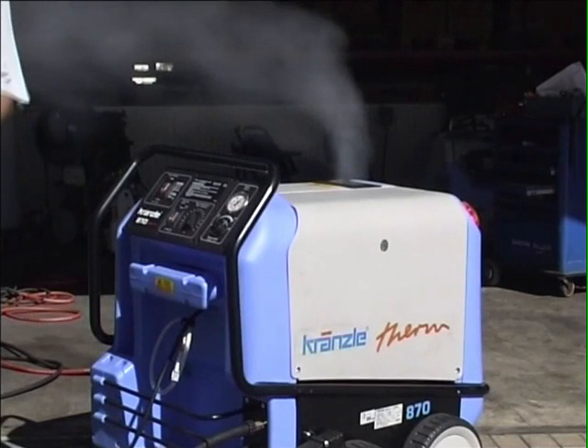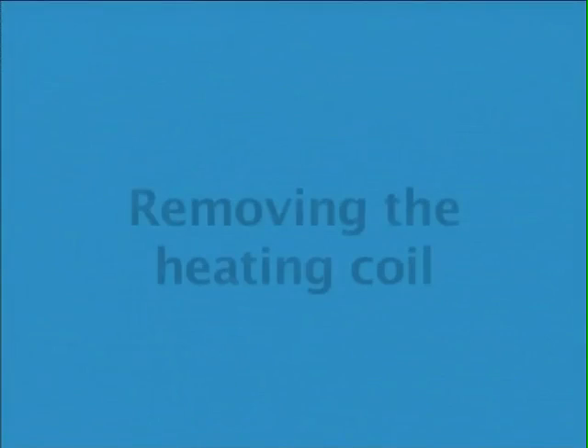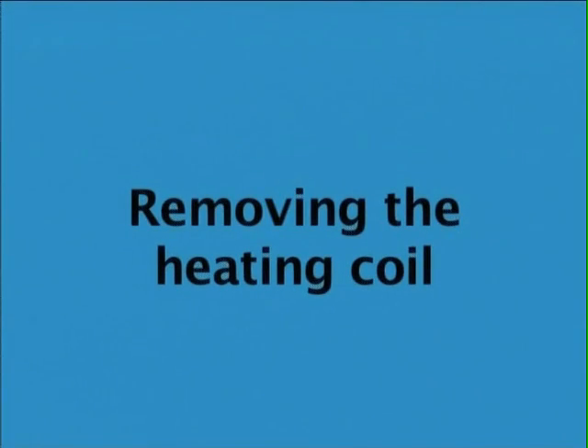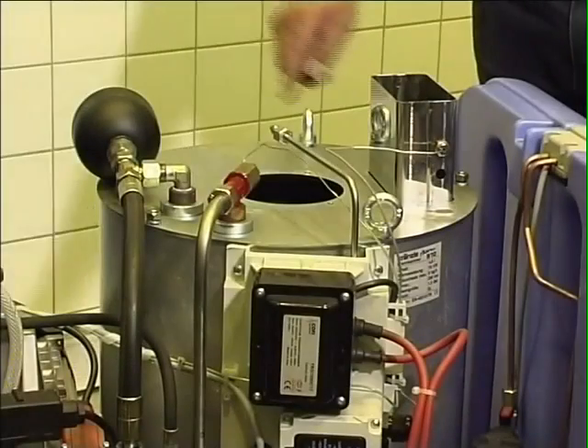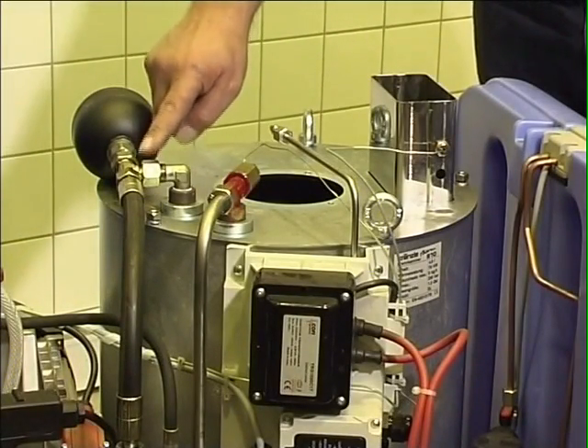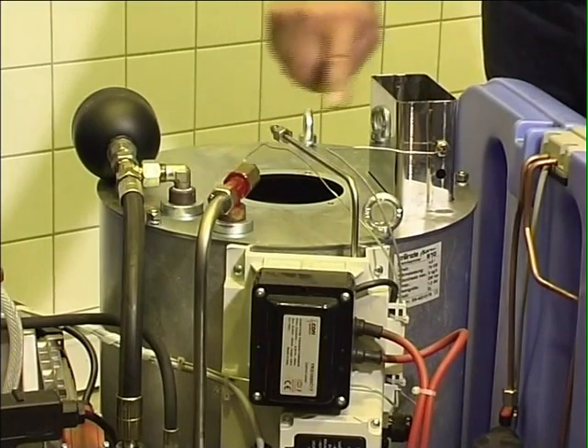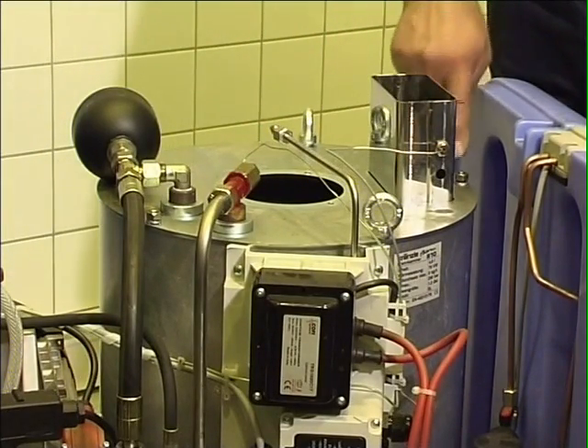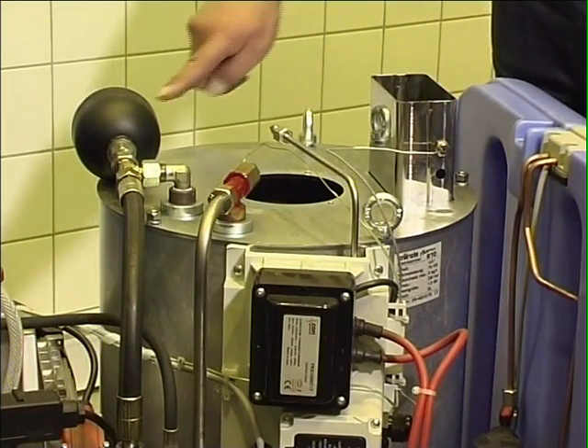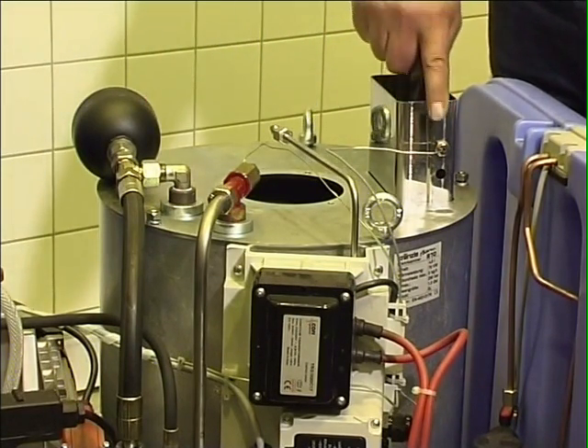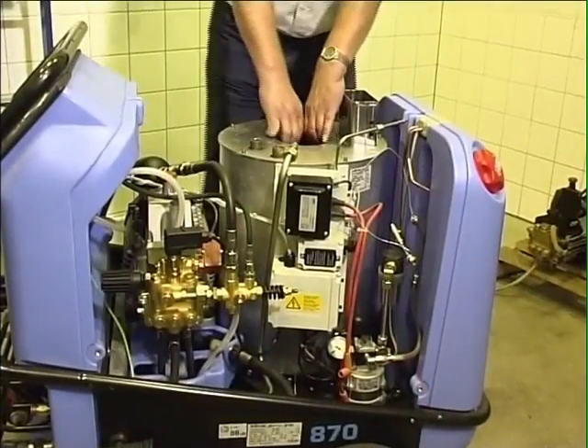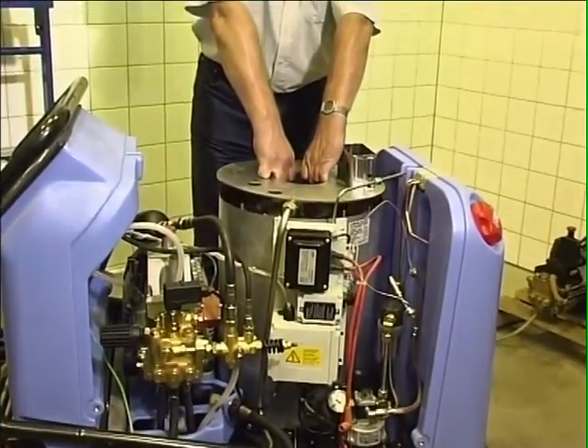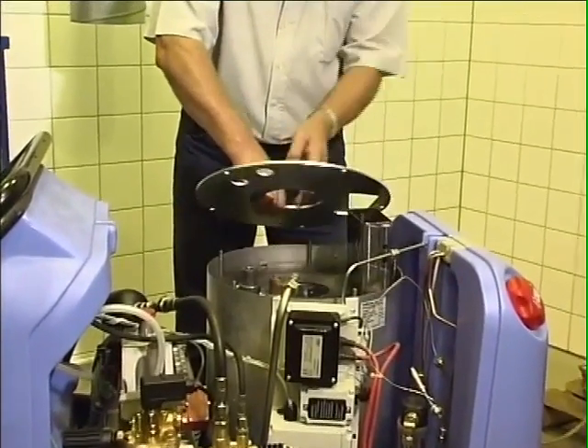Heavy smoke development indicates that the heating coil is full of soot, poor fuel is used, or the insulating plate is full of fuel. As preparation, you must do the following. After you have removed the nozzle stick, loosen the connectors for the heating coil and for the fuel pump, the fixation screws for the outer cap of the heating coil, as well as the probe for the waste gas thermostat. Now you can lift the outer cap. Watch out for the centering edge when installing.